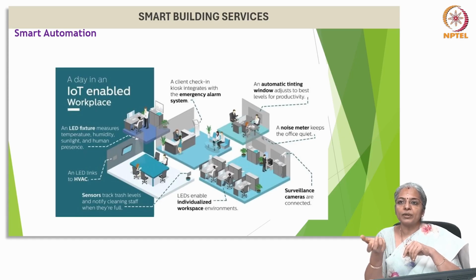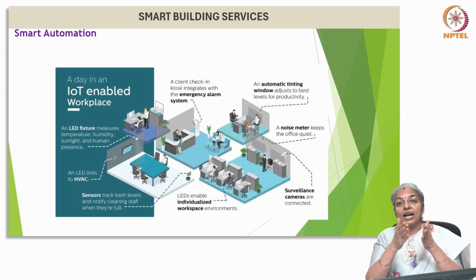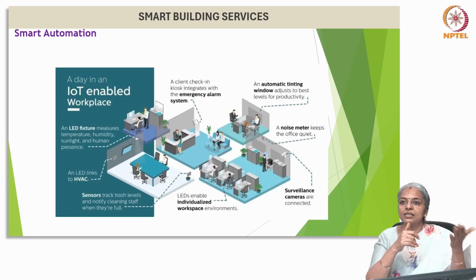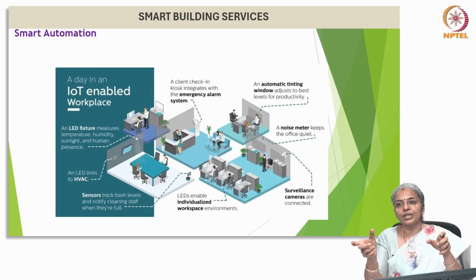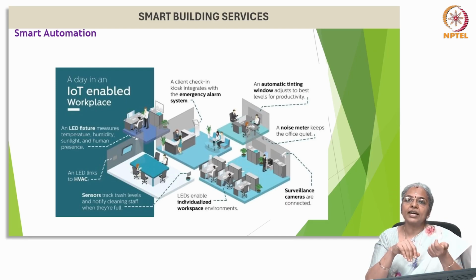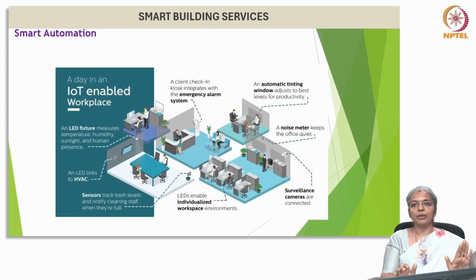While some of the automation systems are more for convenience, there are many others which can reduce energy use by closing even small things such as blinds on a sunny day to prevent heat exchange, or opening the same blinds on cloudy days, which will allow natural sunlight to be used instead of lighting fixtures. They have sensors and automation to determine when is the best time to open or close based on energy consumption and peak times. So, integrating a smart automation system with a smart meter will allow for control of energy usage, and this can reduce energy waste.